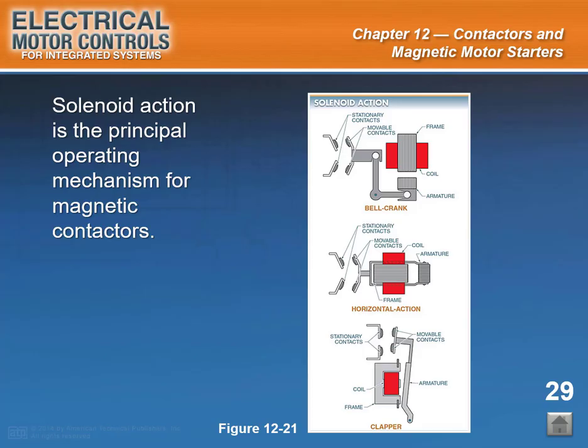Slide caption, Solenoid action is the principal operating mechanism for magnetic contactors. See Figure 12-21. The linear action of a solenoid is used to open and close sets of contacts instead of pushing and pulling levers and valves.